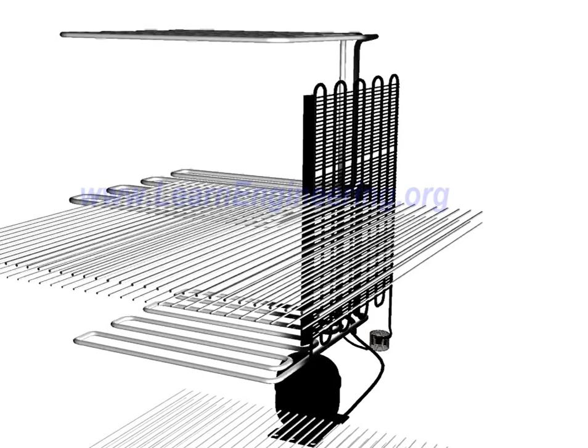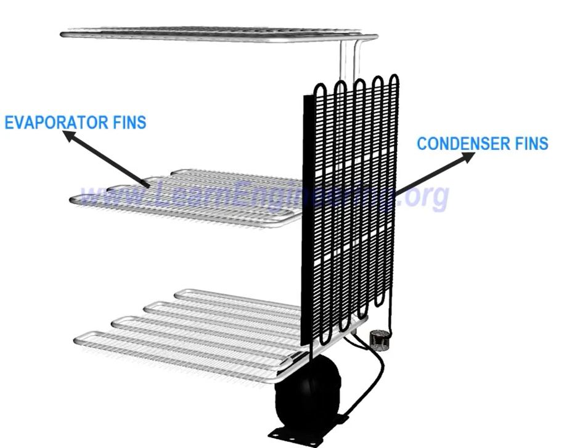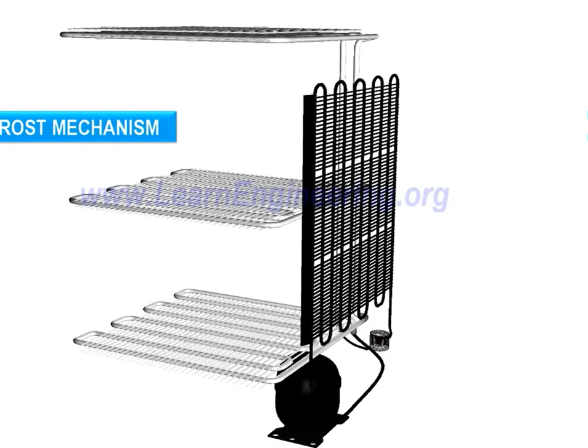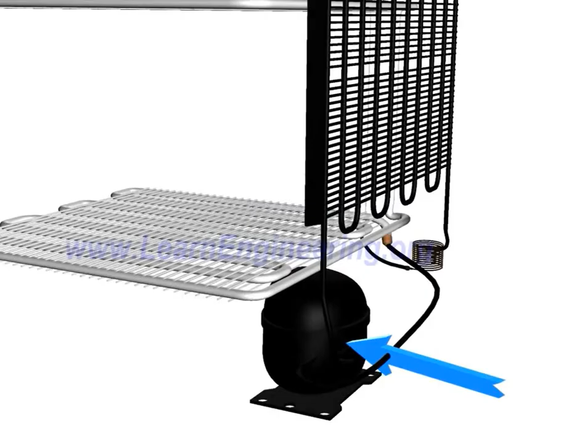You can note more details of refrigerator components here. To enhance heat transfer, both the evaporator and condenser have fins attached to them. Since the evaporator is cooling the surrounding air, it is common that water will get condensed over it, forming frost. Frequent removal of frost is required to enhance heat transfer. Apart from raising pressure, the compressor also helps maintain flow in the refrigerant circuit. Usually, a hermetically sealed reciprocating type with proper sealing is used for this purpose. Since it is compressing gas, a huge amount of input power is required for this operation.